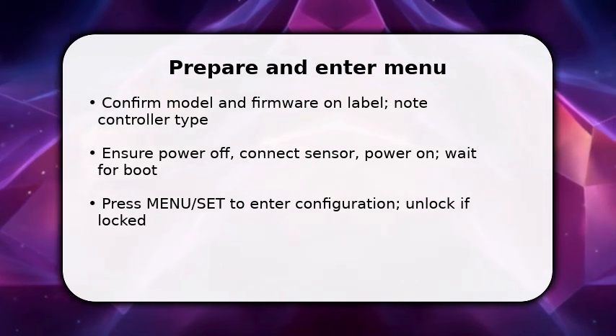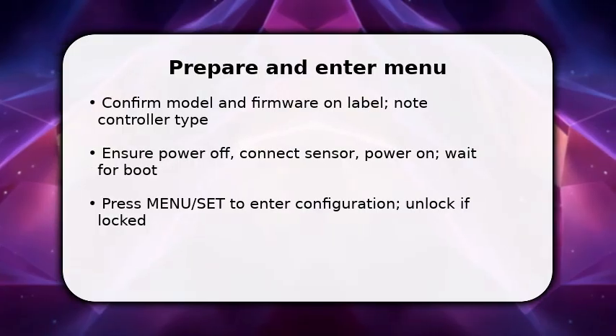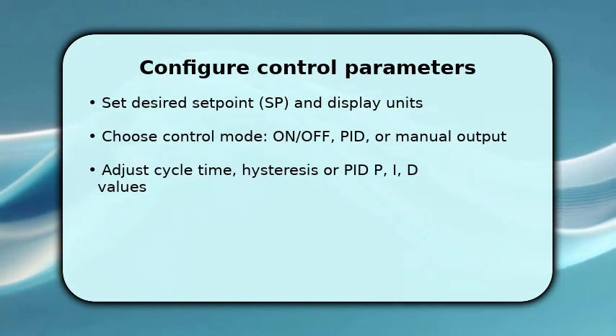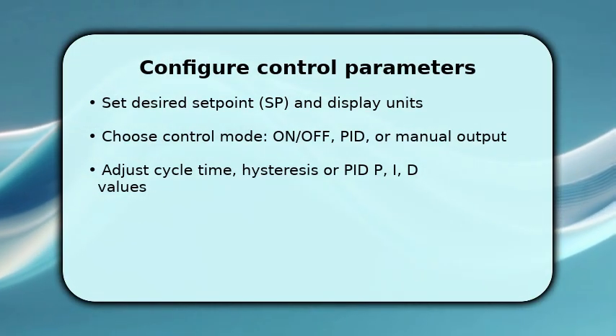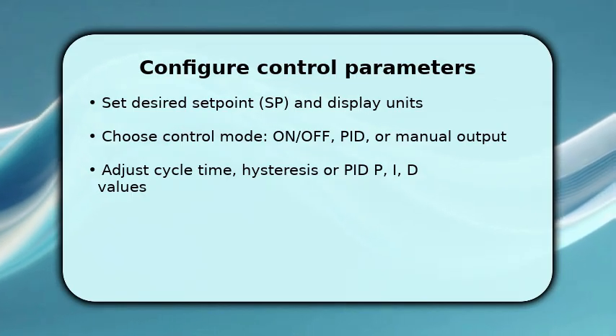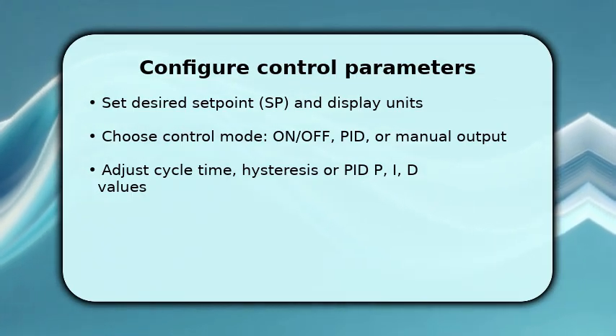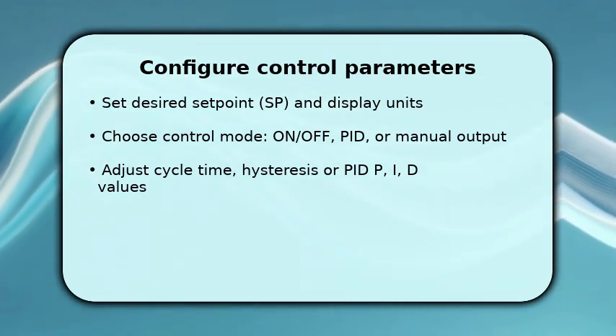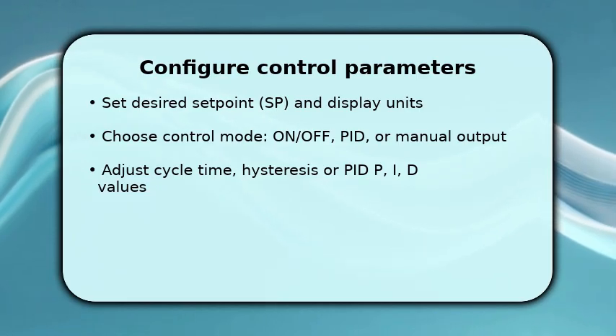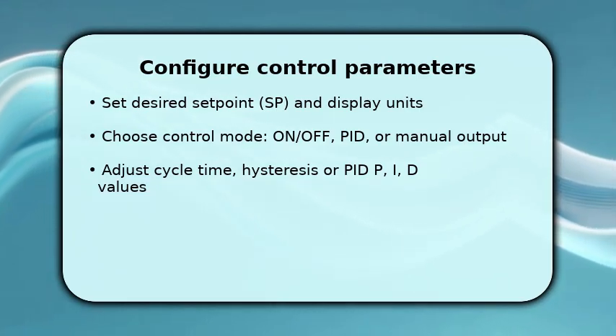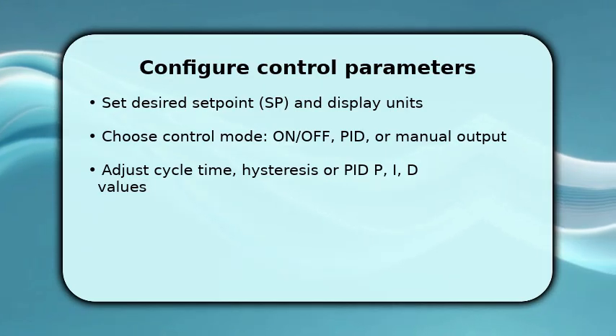You now set the target temperature and the control method. Choose ON/OFF for simple applications or PID for precise control. Once you pick PID, enter proportional, integral, and derivative values, starting with conservative P and I to avoid overshoot. Then adjust cycle time or output update rate and set hysteresis if using ON/OFF.